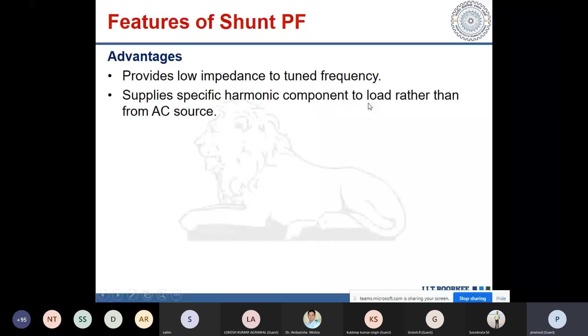It is installed at the AC terminals of rectifiers, drives, and UPS. You may consider any non-linear load, power electronic converters. The LC filter is put in parallel with the load, so the harmonic components of the currents will be absorbed by this LC filter, and the source current will be free from that harmonic. It provides low impedance at the tuned frequency, supplying the specific harmonic component to the load instead of the AC source.